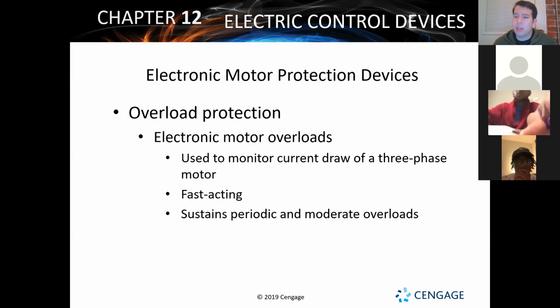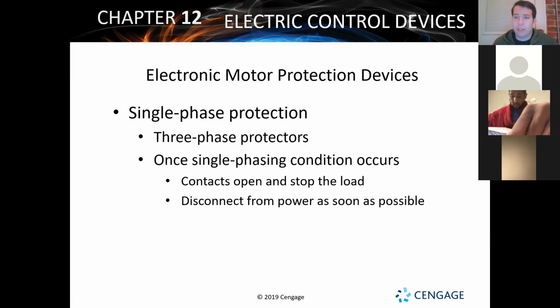There's a couple of different ones we can see used. There's the ones that are going to be for typical things like we talked about last time, a fuse being the most common overload. But they've got electronic control overloads where the board basically is going to react to and stop power from flowing through. And this will be resettable. It'll be able to happen multiple times. And usually it'll also log that information of it shutting down into its data bank or into its error code. The LED flashing would say something about, hey, overload detected coming into the compressor, condenser fan motor, or whatever device that it's trying to protect. These are really, really efficient ways to protect a system from an overload, which again can be a major detriment to its operation and can literally destroy a system. If you throw way too much electricity into it, it's just gone.